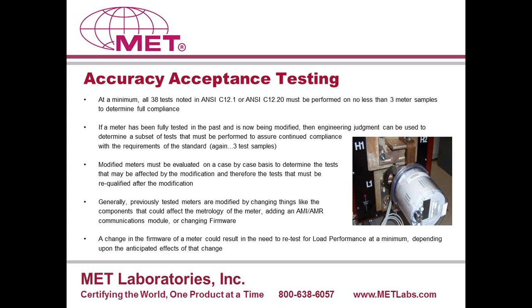The accuracy acceptance testing, again, at a minimum, 3 samples are to be tested for each applicable test. There are 38 tests. Most of the time, all 38 tests do not need to be run for any one particular product. So typically, it's a subset of that. Some tests are not applicable, and we will address that in our detailed test report as well, stating it's not applicable and giving the rationale as to why. So when you submit this report of compliance from a third-party independent lab, it will show that everything was addressed, whether it was compliant, whether it was not applicable, the details of the setup, and so forth.